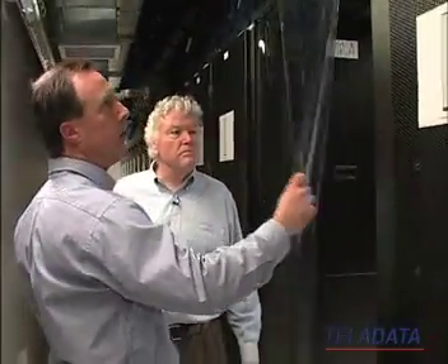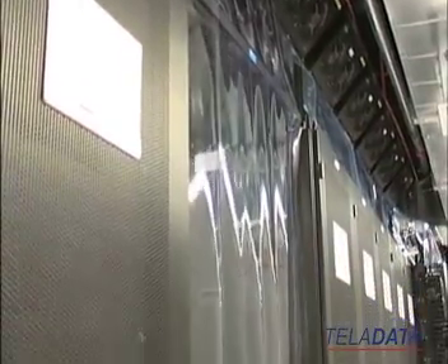So then we came back and installed curtains everywhere, and that seemed to solve 90% of the short cycling problem. I'm looking at the doors here, but it's not just the doors, it's above the racks too. You've buttoned up everything on top of the racks to make sure air doesn't flow over the top as well.